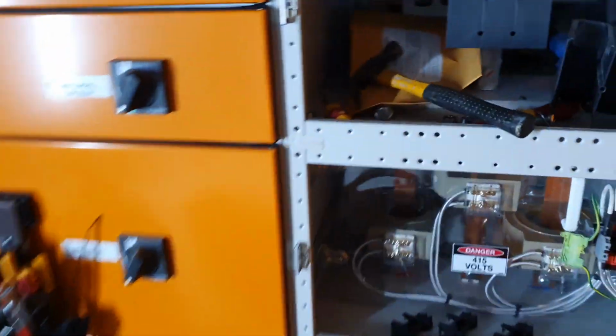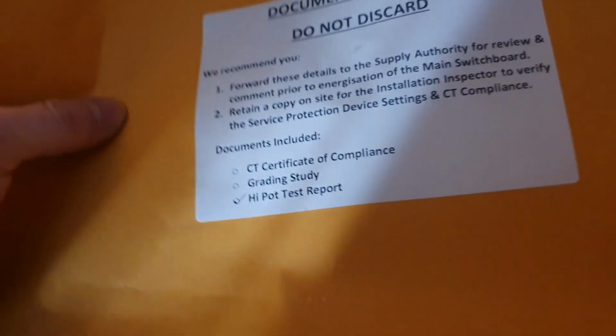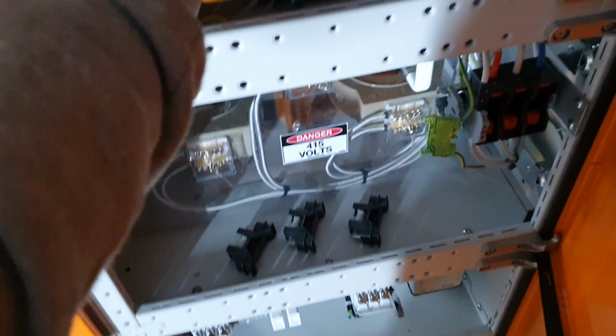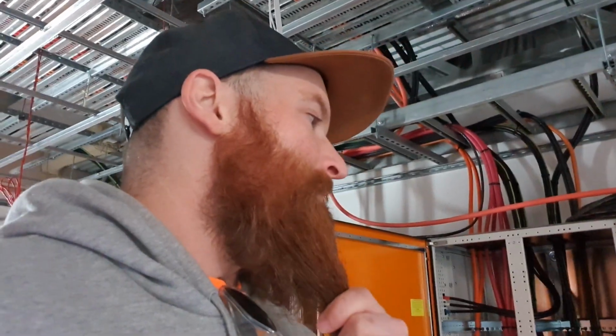I do have a test result from the board builder here - they call it a high potential test. They actually test the boards at 2,500 volts. Maximum we do is 1,000 volts with a megger, but they have a full-on next level high voltage tester that tests these boards between neutral and earth, and they came back with infinite resistance.